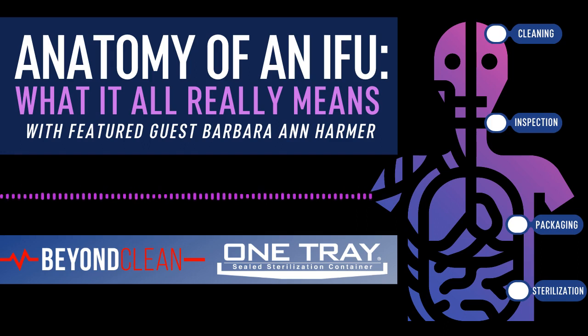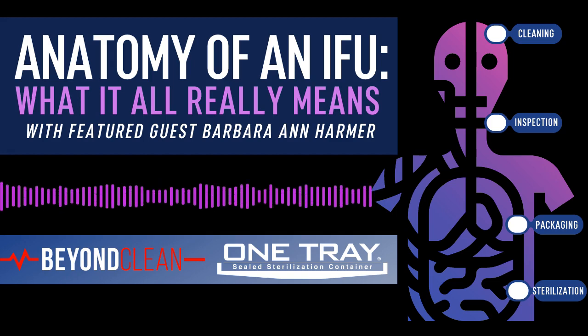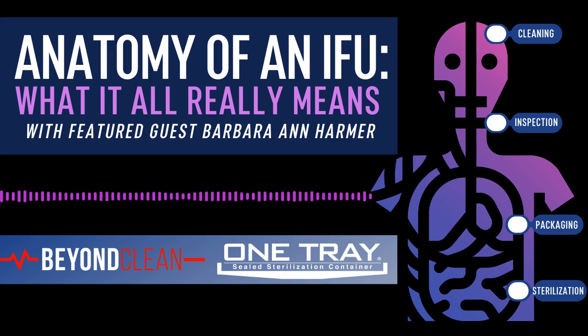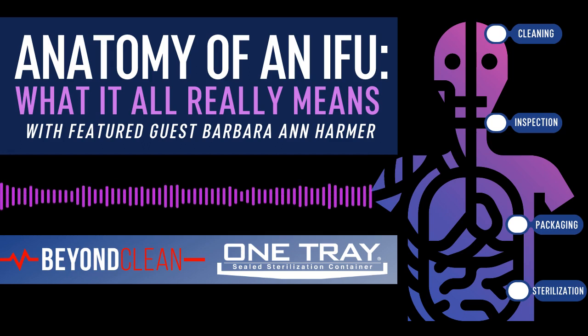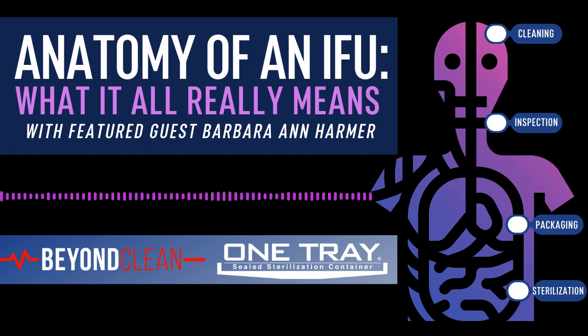Okay, so here's where the confusion really comes in for a lot of people: every instructions for use from one product to another is unique. It's different. And that really ties in well with looking at the ONETRAY as an example that we can walk the audience through right now. What is unique about the ONETRAY and how the information is represented in your instructions for use? I don't know that unique is the right word, because it's absolutely crazy compared to the way that we've worked in this industry up until 2006 when this particular tray was cleared. ONETRAY's IFU specifically addresses that retained moisture in a tray is normal and expected. This is very important information that can certainly be found in the IFU. Important also of note, though, is that the amount of retained moisture is going to be dependent on the load composition.